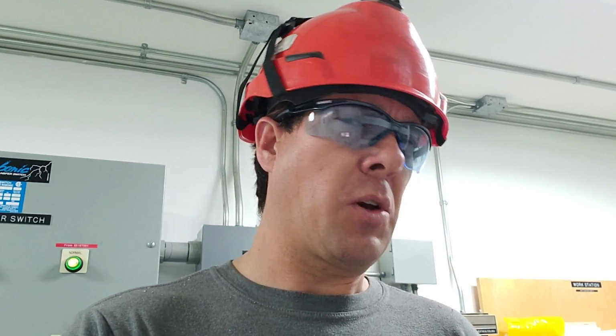So if I get multiple calls from individuals on a line saying the lights went off and on, it could be the recloser, or it could also be a more localized problem. Maybe the tap clamp's arcing enough that the lights went completely off and back on. Sometimes the call will come in dated and timestamped the same as when a squirrel got into a transformer down the road. So I'm pretty confident it was the recloser that caused the light flicker.